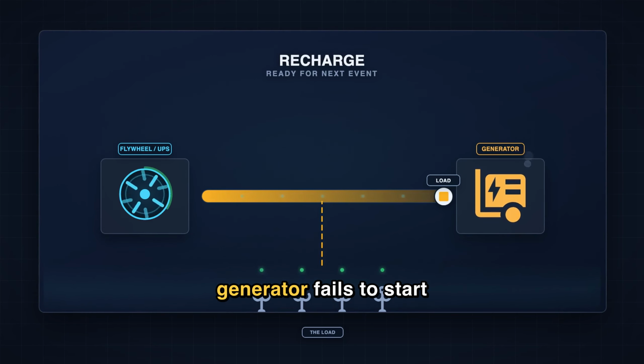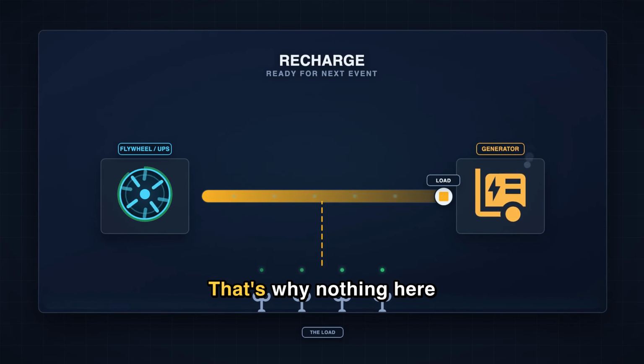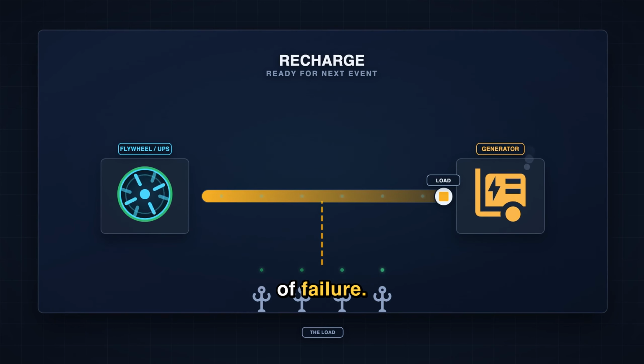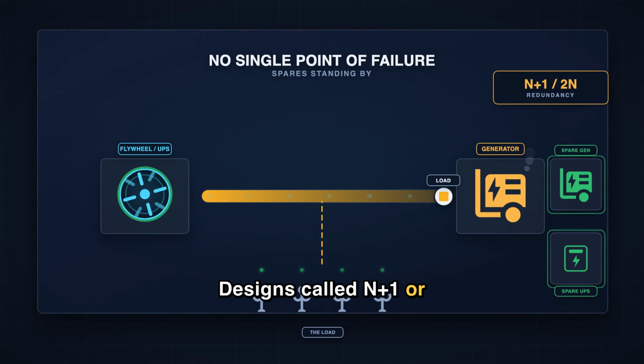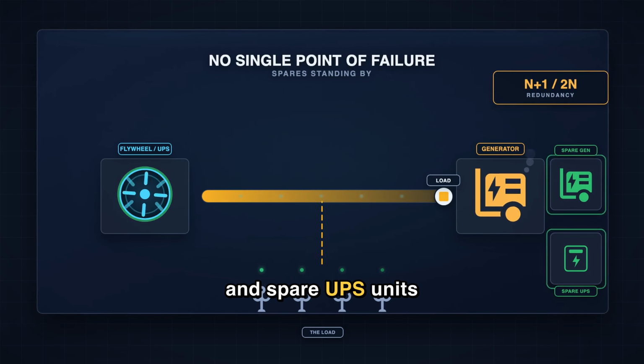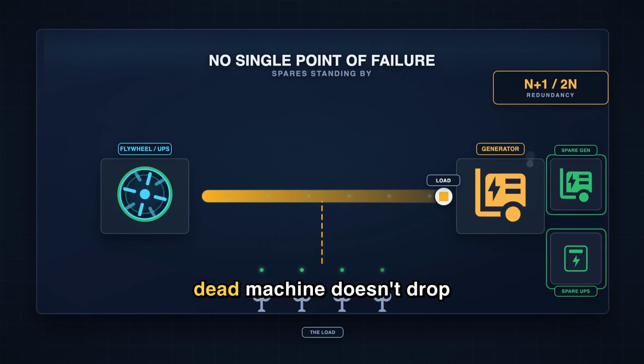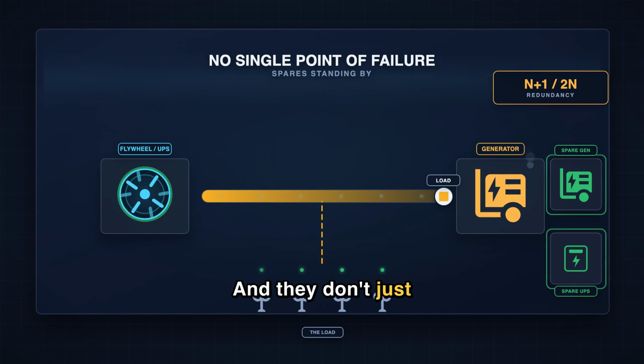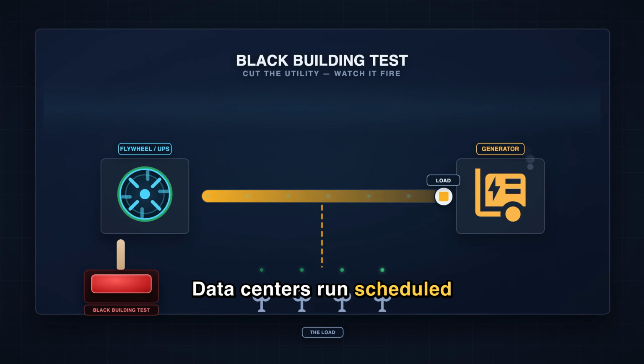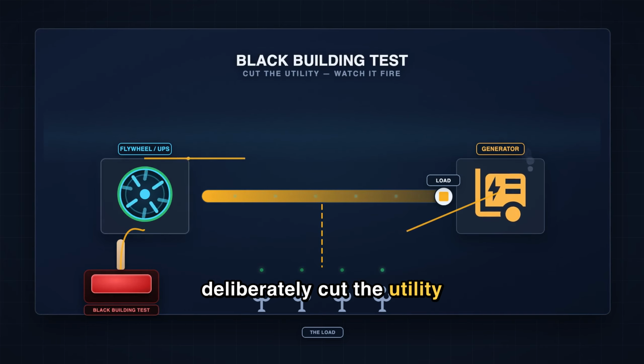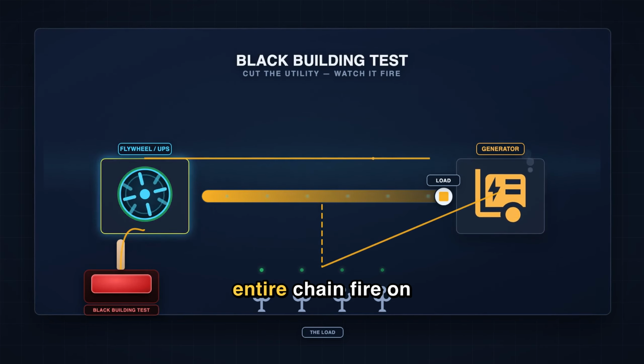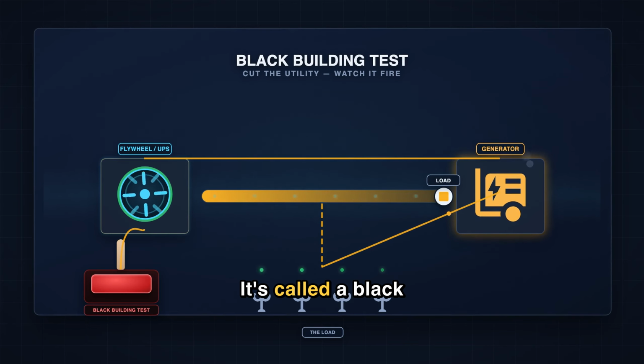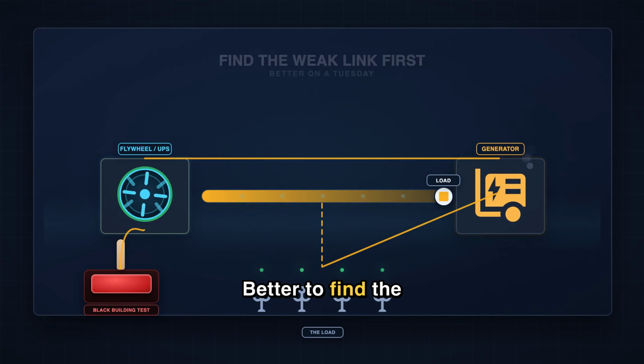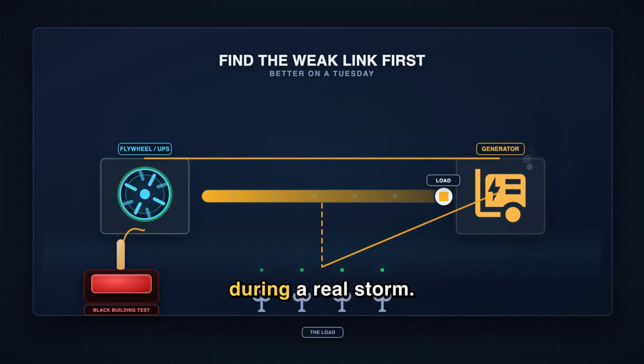But what if a generator fails to start during that swap? That's why nothing here is a single point of failure. Designs called N+1 or 2N mean spare generators and spare UPS units standing by, so one dead machine doesn't drop the load. And they don't just trust it. Data centers run scheduled drills where they deliberately cut the utility feed to the whole building and watch the entire chain fire on demand. It's called a black building test. Better to find the weak link on a Tuesday afternoon than during a real storm.